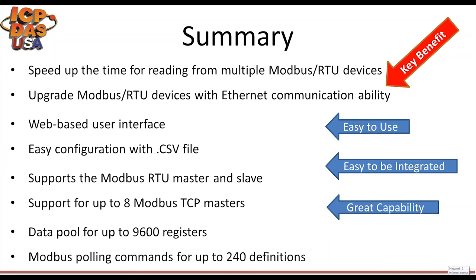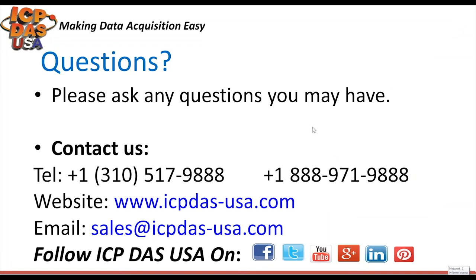To summarize this webinar: Modbus Data Concentrators can speed up the time for reading from multiple Modbus RTU devices and upgrade Modbus RTU devices with Ethernet communication ability, rather than using a Modbus TCP to Modbus RTU gateway. It has a built-in web-based user interface, and configuration can be done using an Excel spreadsheet. It also supports up to 240 Modbus RTU commands from Modbus slave devices through RS-422 or RS-485, and supports up to 8 Modbus TCP masters.